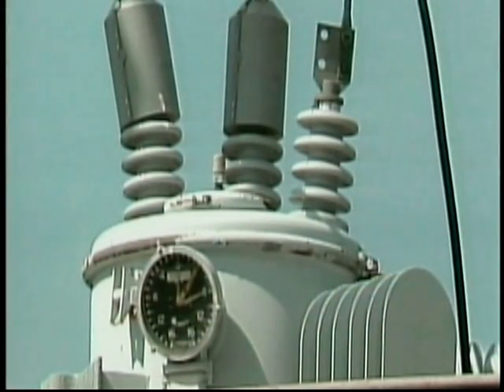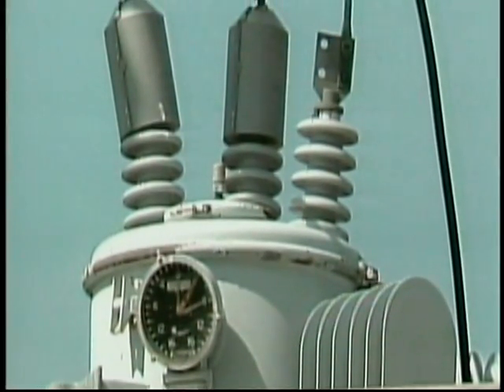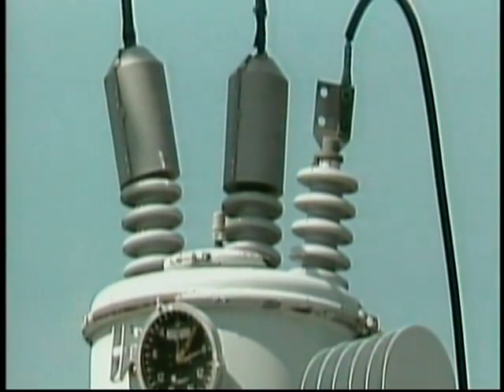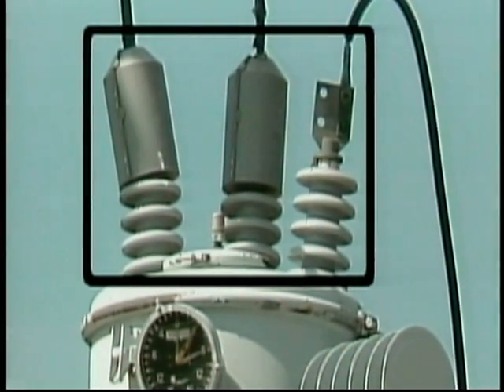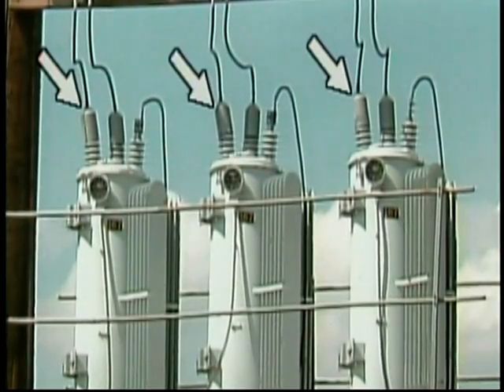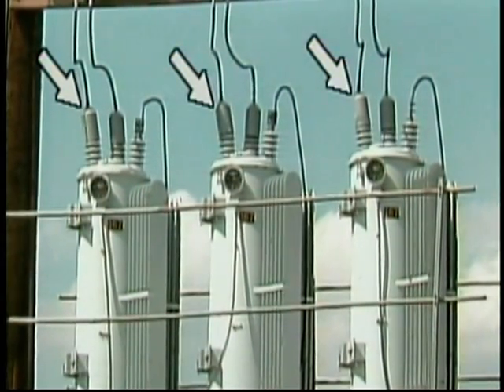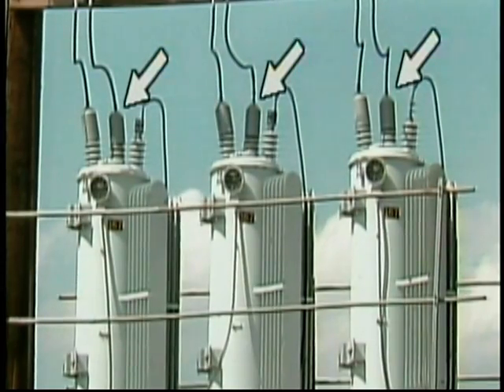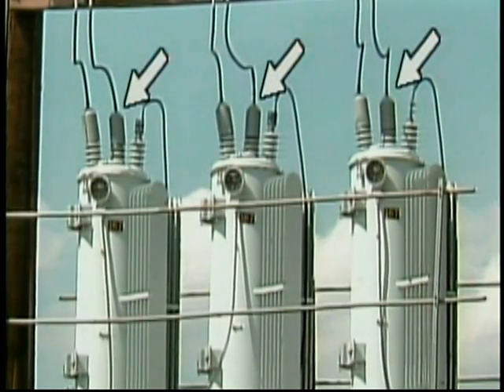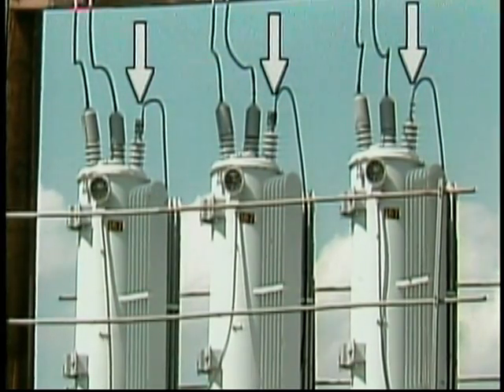One of these is the bushings. A single-phase voltage regulator typically has three primary bushings and no secondary bushings. One bushing insulates a phase source connection to the regulator. Another bushing insulates the regulator output connection to the phase. The third bushing insulates the regulator connection to ground or to another phase wire.